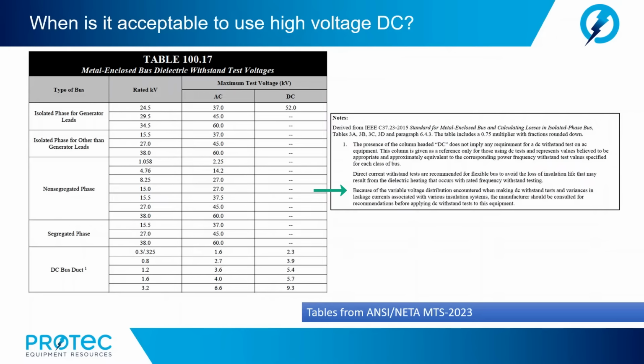Now, because of the variable voltage distribution encountered when making DC withstand tests and variances in leakage current associated with various insulation systems, the manufacturer should be consulted for recommendations before applying DC withstand tests to this equipment.